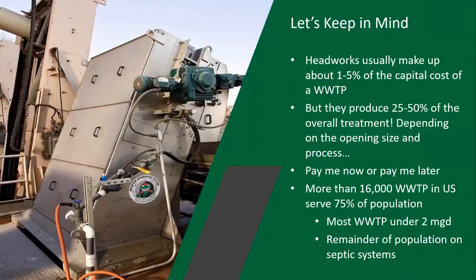Thanks, Stacy. So first, I want to give you a couple of things to keep in mind as we go through the session. These are just some insights that should help you put into perspective a lot of the things that we'll talk about. When we talk about new water treatment plant projects or wastewater treatment plant rehab projects, the capital cost of headworks screening equipment is really only about 1 to 5% of the overall budget. So it's not a lot. But your headworks is going to produce between 25 and 50% of the overall treatment. That does depend on the opening size and the process, but it's very important.